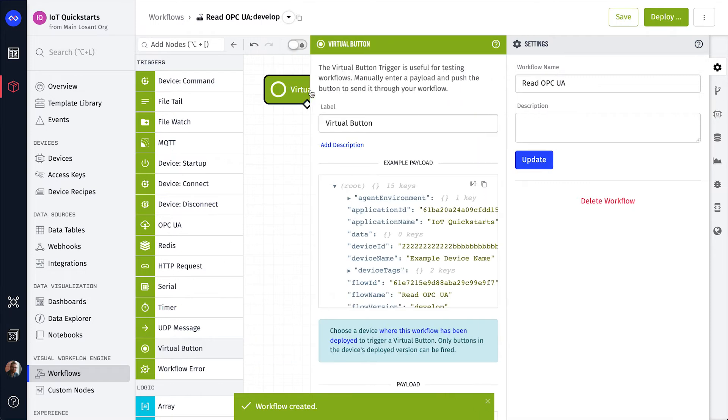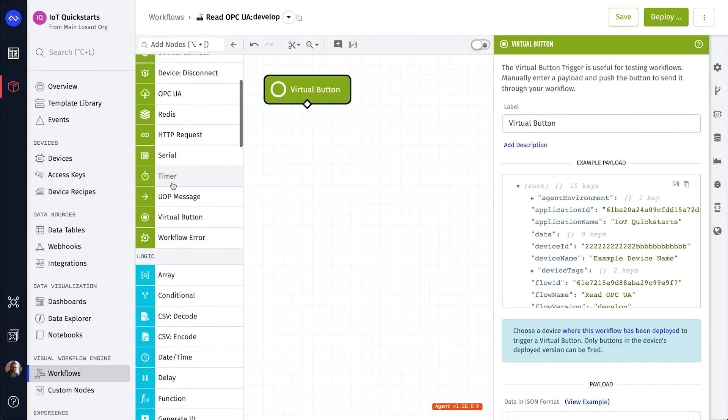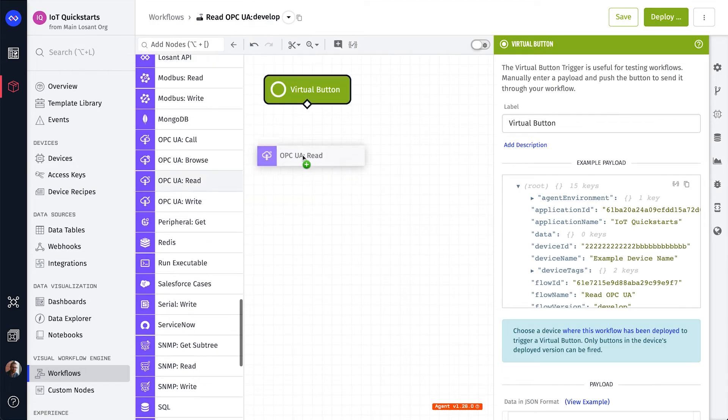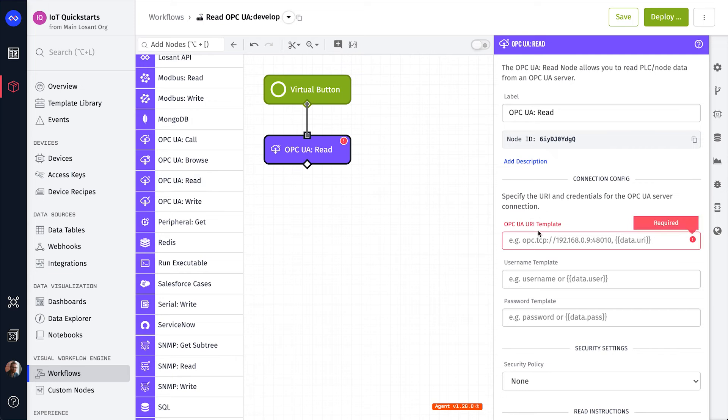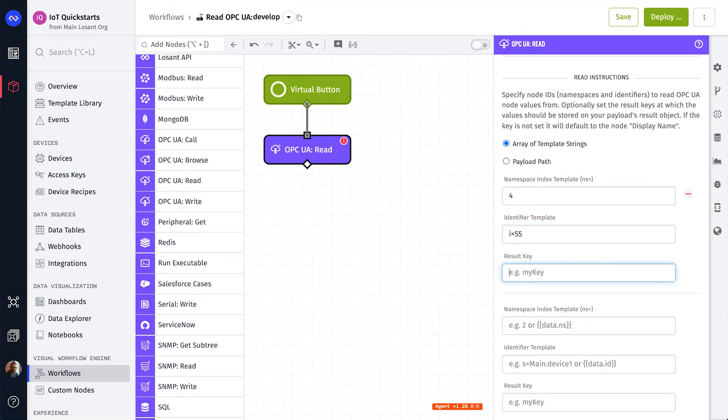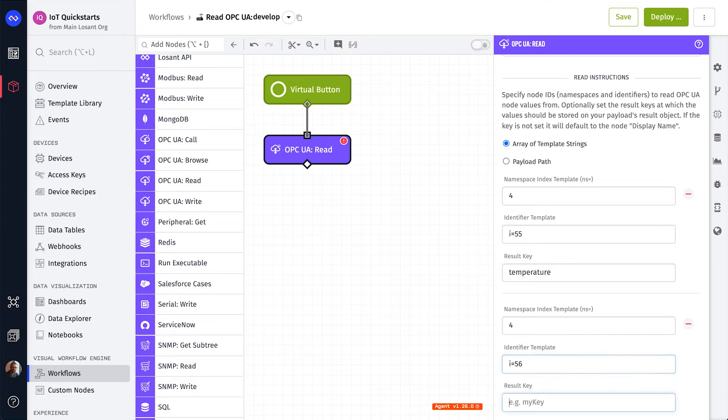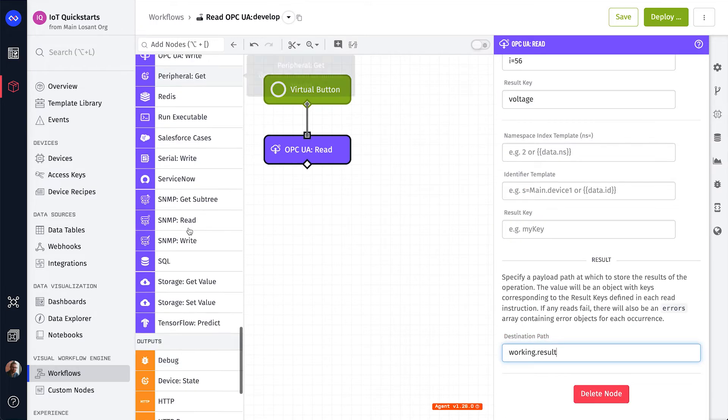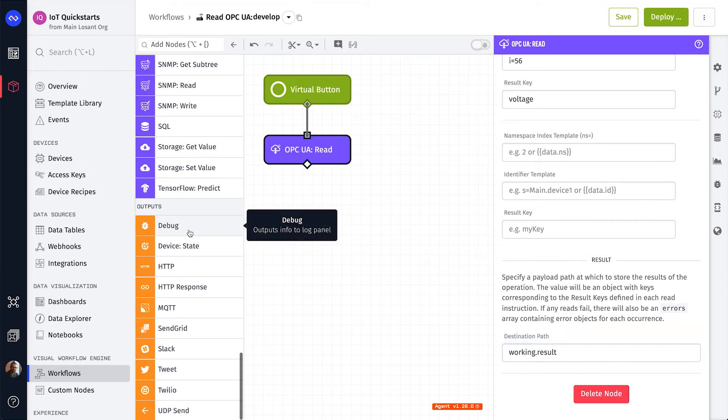Let's start with a Virtual button so we can run this workflow manually. Next, add an OPC UA read node. For this PLC, we need to set the URI and the details of the two nodes we want to read. We'll place the result on the payload at working.result. Finally, add a debug node so we can see the payload at runtime.